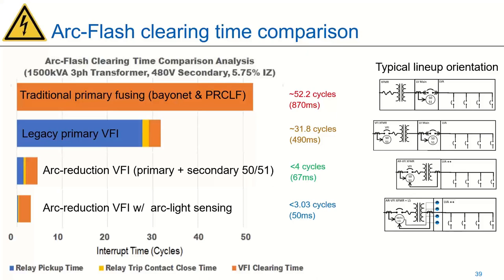There are, of course, residual ground fault settings. You can look for an imbalance, things like that. But really, if you're able to sense that, even if it is a lower magnitude, that's where the beauty of these microprocessor relays comes in: you can lower and tailor that to that specific design. And that's another thing that's helpful when an integrator, an engineering firm, or a manufacturer like Eaton in this case gets involved. We can help size those components to make sure that works properly.